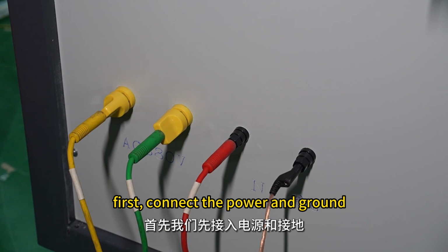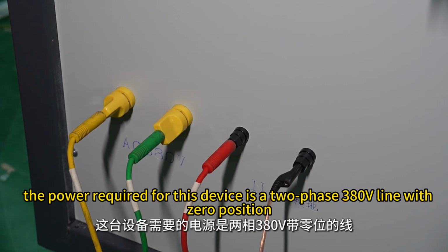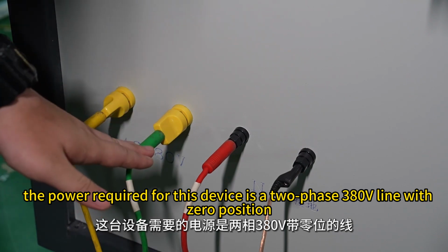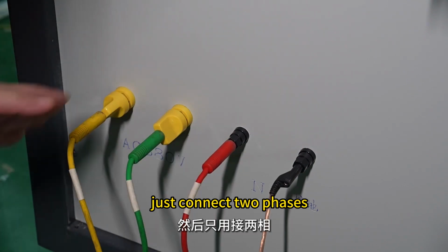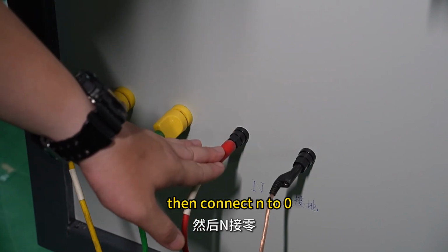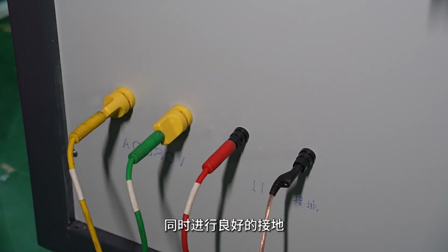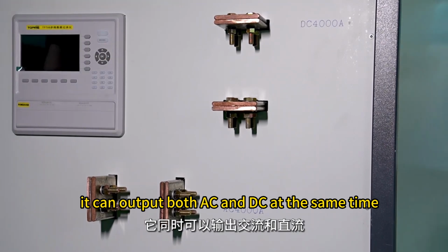First, connect the power and ground. The power required for this device is a two-phase 380 volts line with 0 position. Just connect 2 phases, then connect N to 0, and ensure good grounding. It can output both AC and DC at the same time.